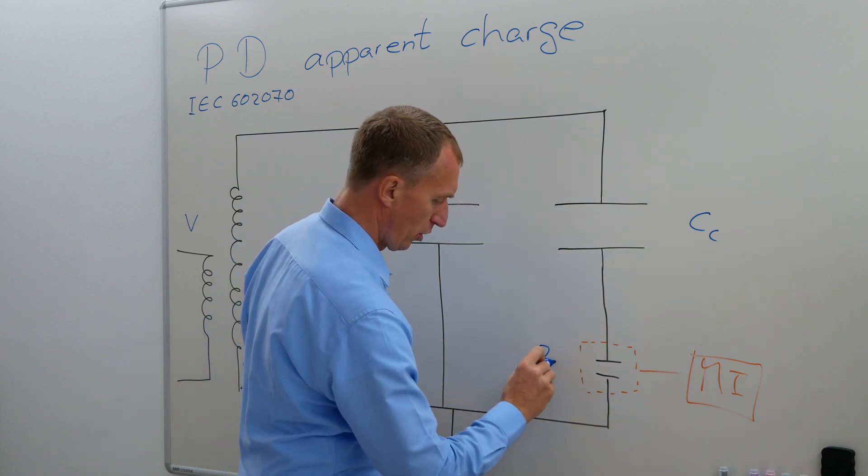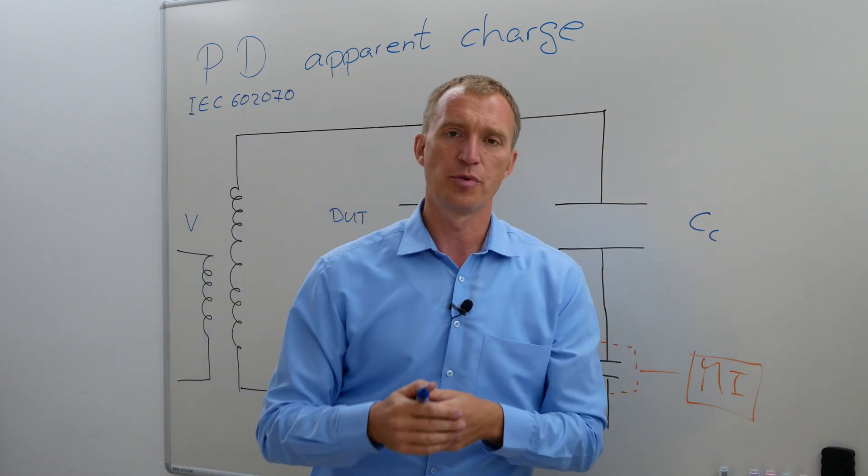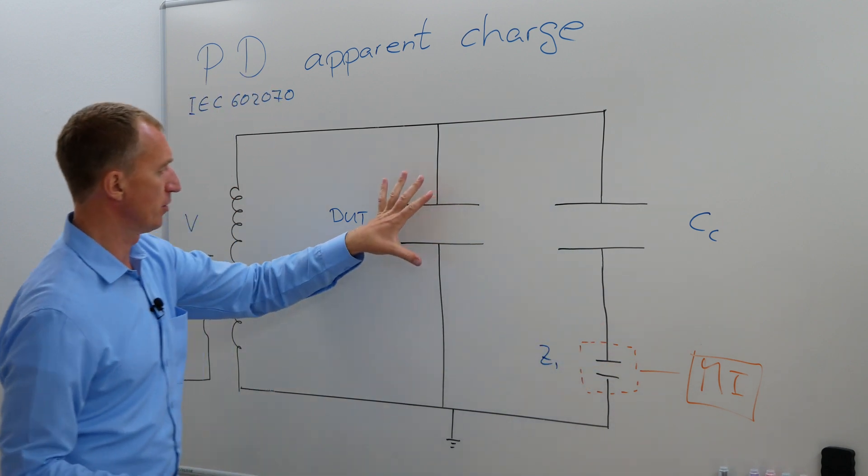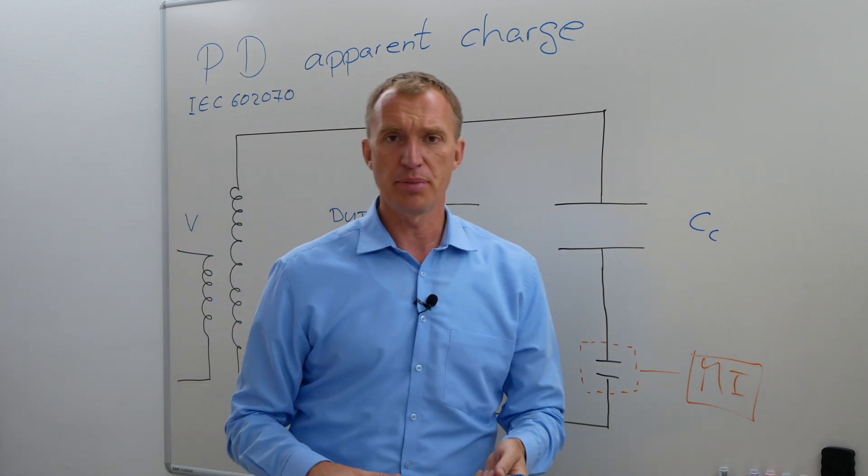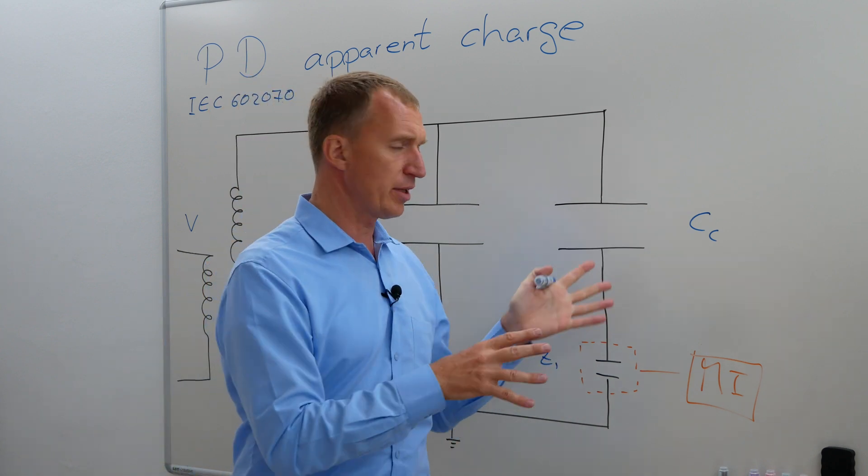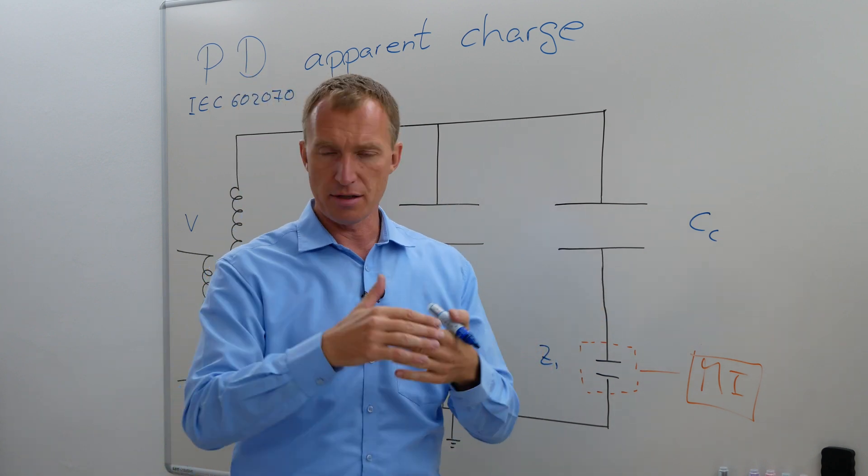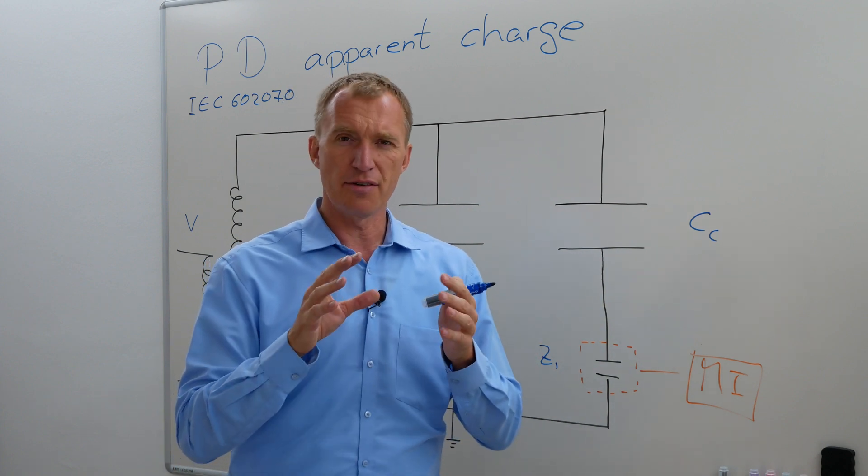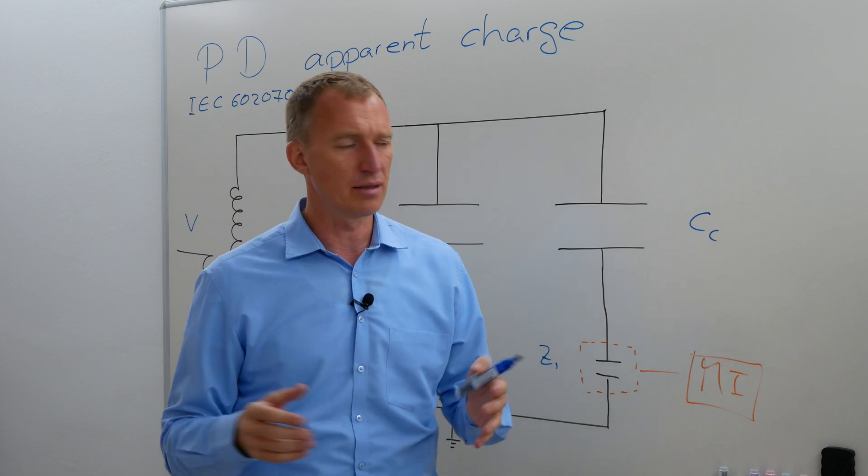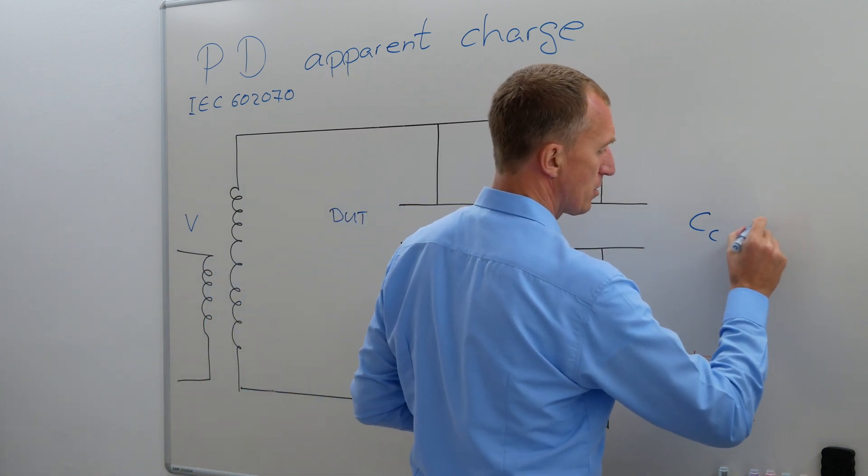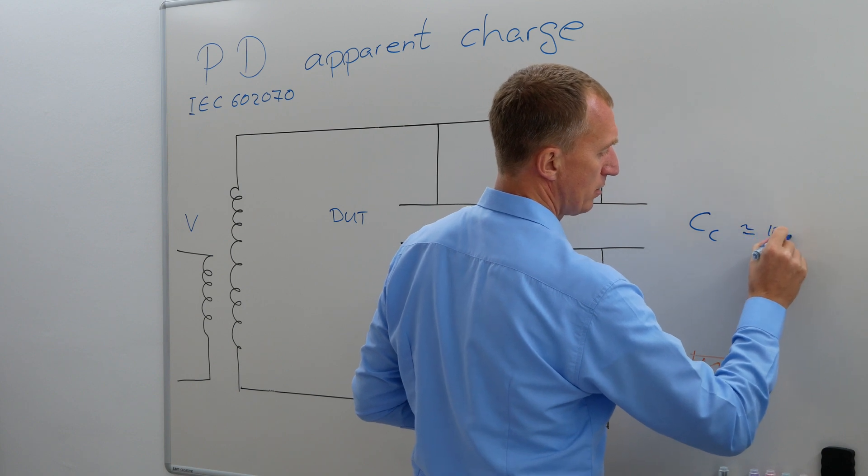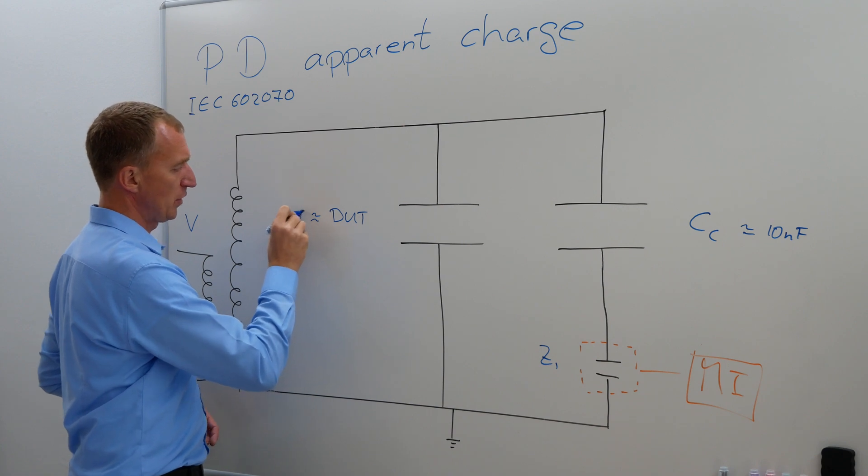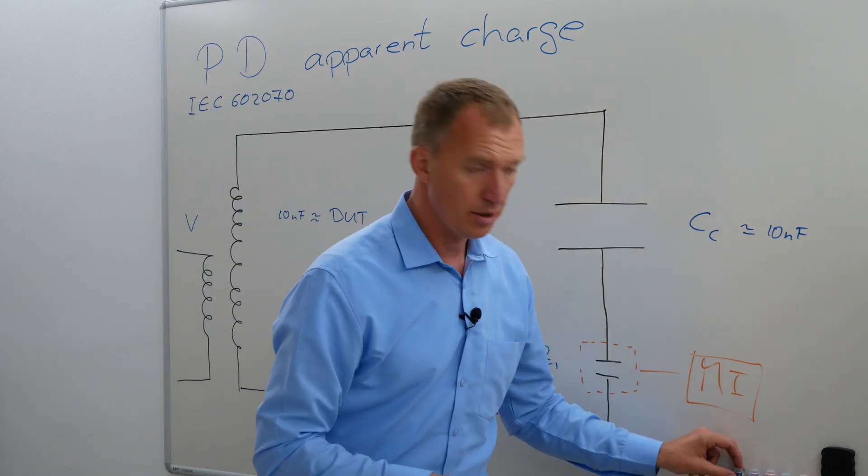And this one over here is very often called measurement impedance. However, the majority of people I know, they call it a quadrupole. So coupling capacitor, quadrupole, device under test. And now let's imagine for the time being that the device under test and the coupling capacitor are just a capacitance, a pure capacitance, no resistance, no impedance in there. And let's imagine for the time being that they have around the same capacitance, around 10 nanofarad.